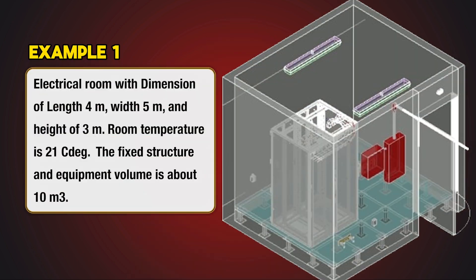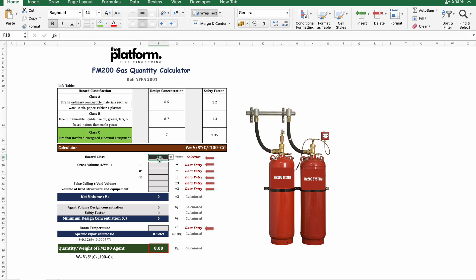Let's take the first example to show you how to use the calculator and get the different variables. We start by defining the class of the protected hazard. The electrical room is classified as a class C hazard, hence the design concentration is 7 and the safety factor is 1.35 according to NFPA standard.